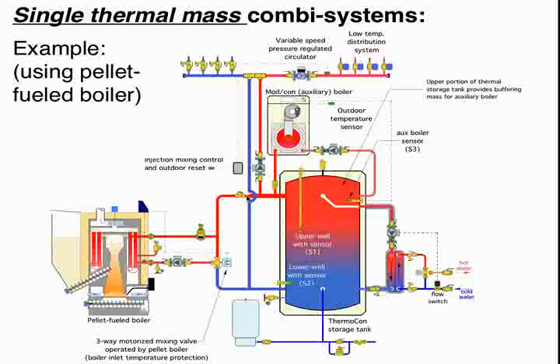So there's a case where the buffer tank is essentially always being maintained. But that is kind of a special application. A pellet boiler just doesn't turn on and off like an oil boiler or a gas-fired boiler would. If you have a low-mass gas-fired boiler, the only time I'm trying to think of a scenario here where it would make sense to maintain the load, maintain temperature in the storage tank.